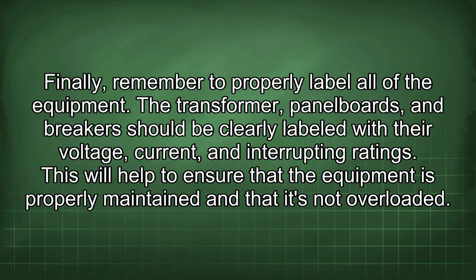Finally, remember to properly label all of the equipment. The transformer, panel boards, and breakers should be clearly labeled with their voltage, current, and interrupting ratings. This will help to ensure that the equipment is properly maintained and that it's not overloaded.